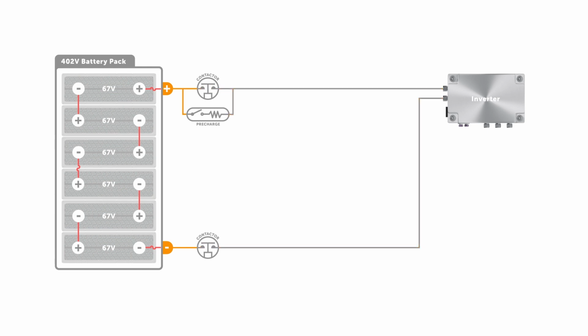The pre-charge circuit instead runs the current through this relay and a resistor, along with one of the other main contactors, to slowly charge the high voltage bus. Once the BMS detects that the bus voltage is close enough to the battery pack voltage, it will close the other main contactor and then open the pre-charge relay. If during pre-charge the voltage doesn't come up at all, the BMS will throw a fault and reopen the contactor and pre-charge relay. Often, the pre-charge resistors aren't designed to carry current for extended periods of time, so it's important that the BMS be configured correctly to prevent blowing this resistor.